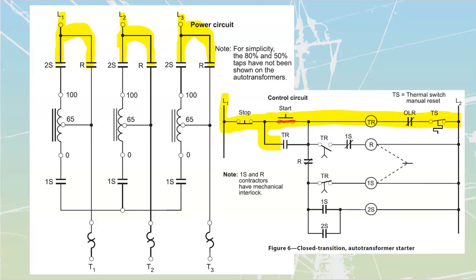As soon as we apply power to the timing relay coil, we are going to have the instantaneous operation of this over here, which is going to seal in. At the same time, we are going to have current pass down through here, because this is normally closed, down to each of these contacts that we see over here. Then it's going to hit this one, which is also normally closed. It's going to be able to pass through that, which is going to power up our 1S coil. Once it powers up our 1S coil, that is going to close and power up our 2S coil. So the instant it hits, the 1S is going to fire this closed, which is then going to close the 2S coil, which is then going to seal itself in like this.